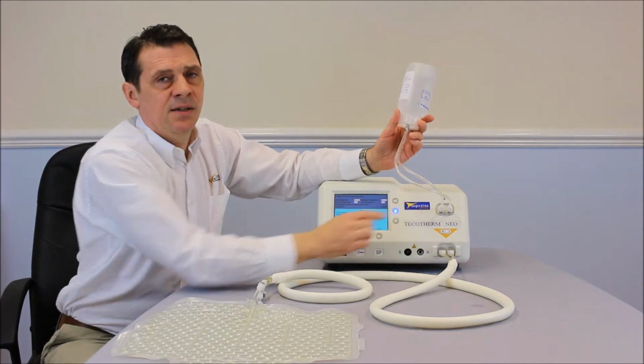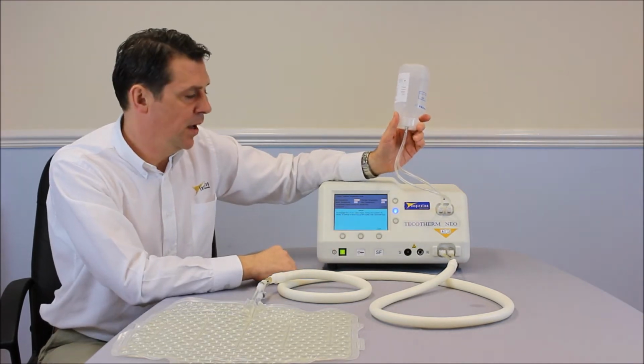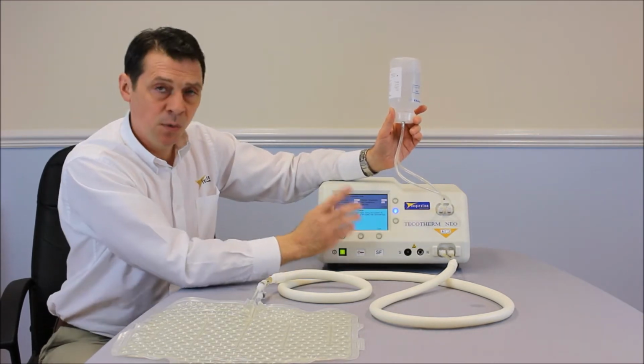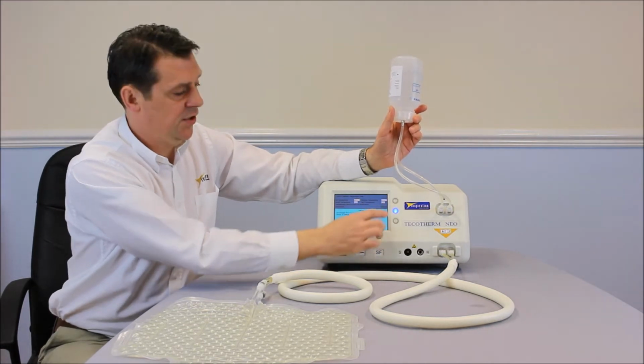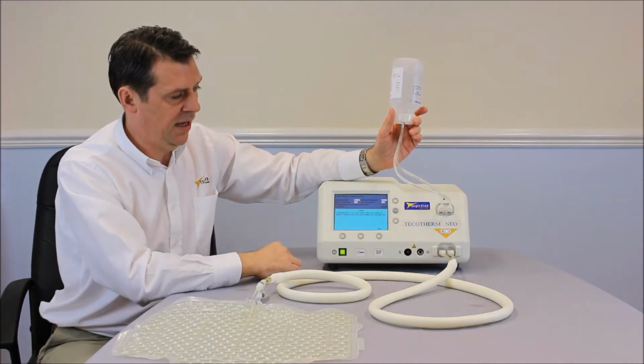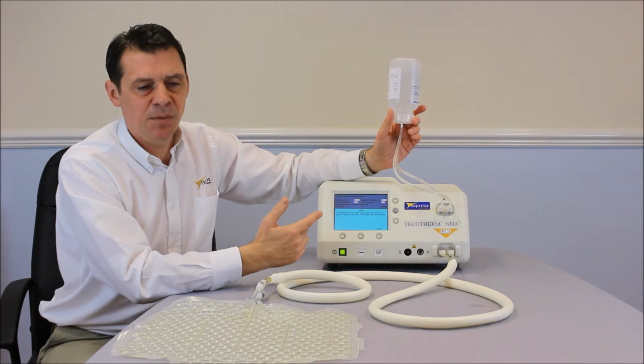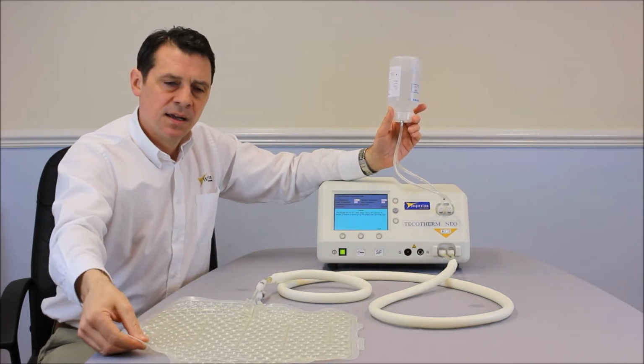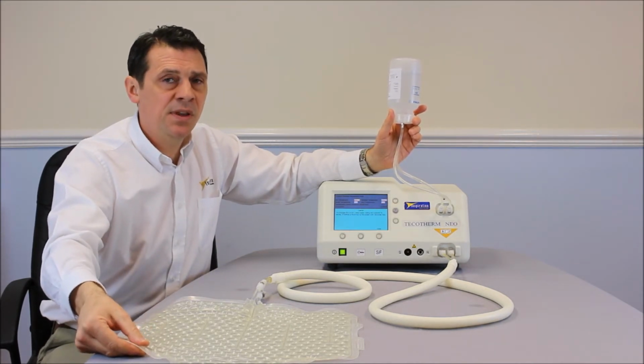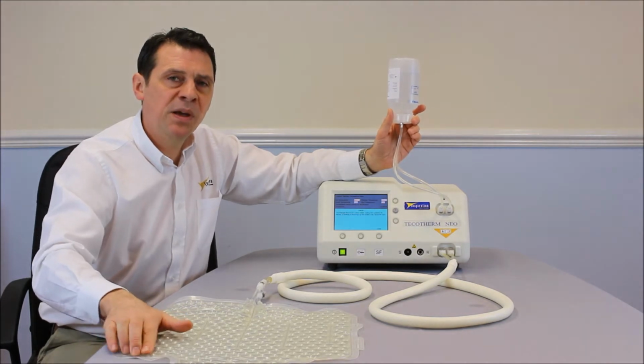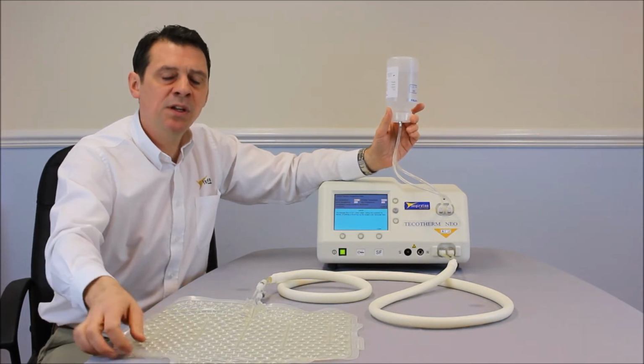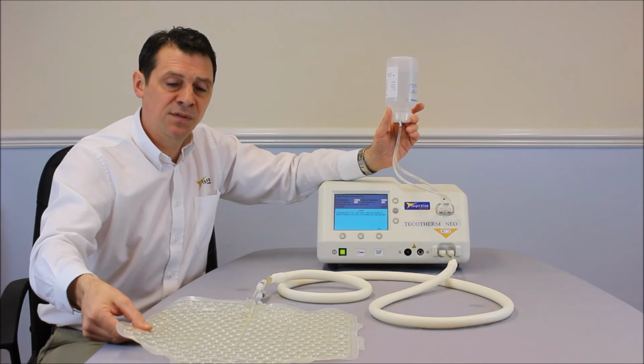Whilst we've connected these two, we may get an error alarm just telling us that those hoses are connected. We accept this and press close or confirm here. That will allow us to continue the fill up. This may take a few minutes with an empty mattress, if we're just topping up maybe 30 seconds to 2 minutes, but you must use your judgment not to overfill or underfill.